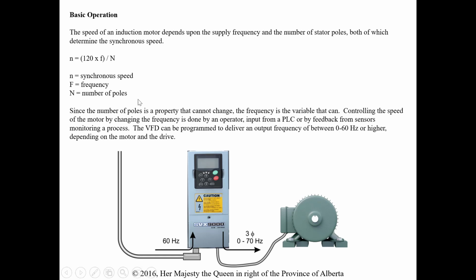So the basic operation, this is a formula we've talked about for getting our synchronous speed. That's 120 times the frequency divided by the number of poles. So it's the frequency and the number of poles that are going to determine the speed. And again, we can't change the number of poles once that's decided. Obviously, that's a set thing without literally manufacturing the motor itself. So the only thing we can do is change the frequency.